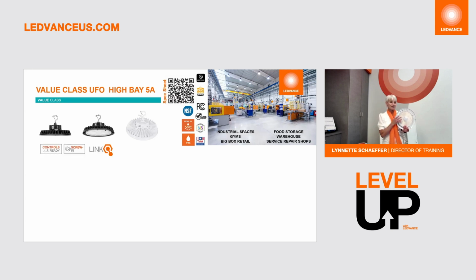Now, the other thing that's pretty neat about this product is that it is controls ready. I know you guys have heard me talk about controls ready, but just as a quick reminder, controls ready means you can easily add standalone or network lighting controls without the need for any electrician, and you can add it whenever you want. There's no special wiring. You just bring regular power to the luminaire, and then you take your handy screwdriver and you unscrew the cover here. That exposes a little receptacle. This is a screw-in receptacle. So I can take a standalone control solution and simply screw it in.